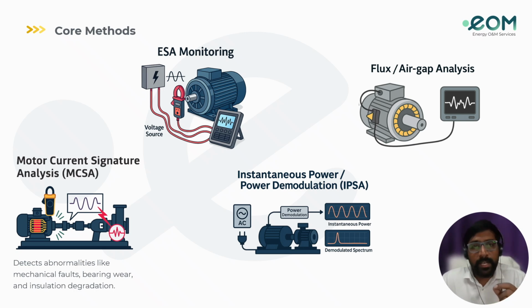And the next method is instantaneous power or power demodulation, IPSA. This power demodulation is used for rotor faults, is robust under varying load, and is used in protection relays as well. It also tells you about broken rotor bars, and the power spectrum shows the 2F sidebands around the frequency, like electromagnetic torque pulsation. Gear faults show peaks at the gear mesh order and sidebands as well. It also tells you about resonance and misalignment, and gives a direct window into mechanical health via the electrical signature.